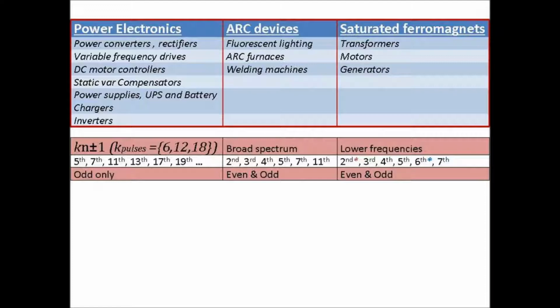Arc devices are, as I said, all over the shop. Even and odd harmonics come up here: 2nd and 3rd, 4th, 5th, 7th, 11th, you name it, it's probably there. And even worse, they have some below the fundamental 50 Hz frequency, which is the subharmonic domain, as some people call it. And that tends to give out voltage fluctuations which lead to flicker. So you can end up having your light going on and off a lot of times in your room, and people find it pretty annoying.